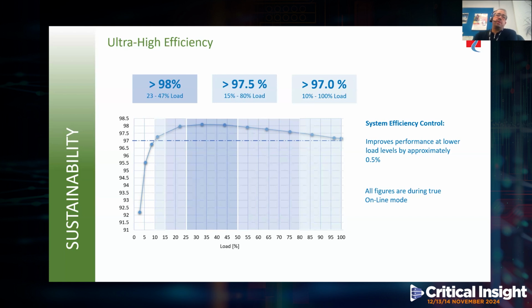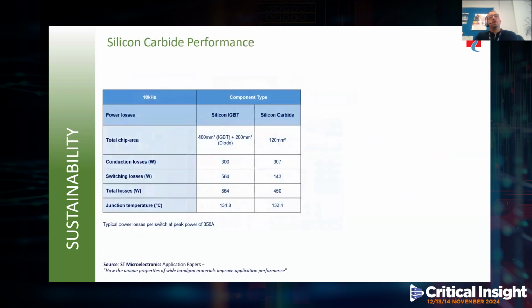And so one thing we always say to people is always make sure that the figures being shown are correct and they actually suit your application, which in most cases is going to be online double conversion. Now, the main change which has enabled us to produce a UPS with such high efficiency is the implementation of silicon carbide. Now, the table here compares a typical silicon device versus a silicon carbide device and highlights the key differences. From this, we can see that the overall chip area is reduced by approximately 80%. So the silicon carbide devices are much smaller.